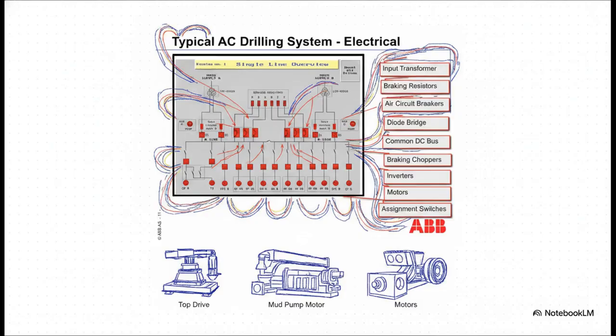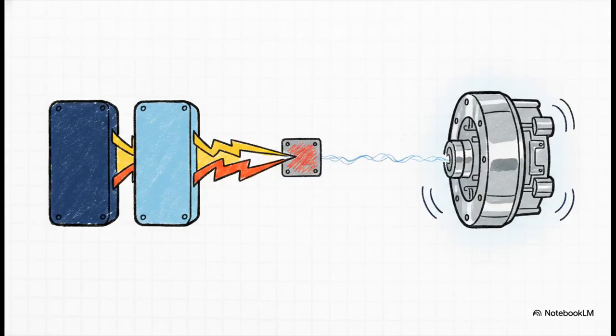It maps perfectly. But there is a critical engineering reality you must never forget: the weak link warning. Every single watt that turns your drawworks goes through that entire 5-step chain, which means the entire power path has to be sized together. If you have an undersized transformer or even a poorly rated feeder breaker, it's going to instantly throttle your drawworks performance. It doesn't matter if you bought the most expensive top-tier variable speed drive on the market—a great drive simply cannot overcome a bottleneck upstream.